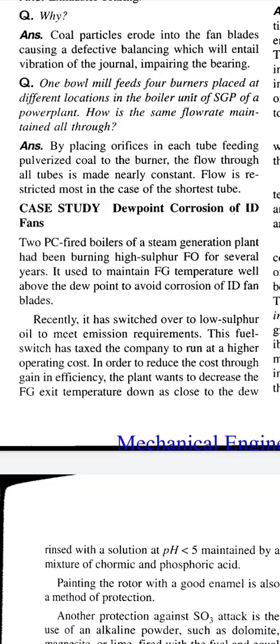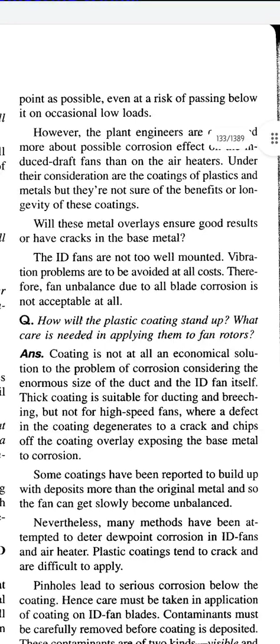This fuel switch has forced the company to run at a higher operating cost. In order to reduce the cost through gain in efficiency, the plant wants to decrease the FG exit temperature down as close to the dew point as possible, even at risk of passing below it on occasional low loads. However, the plant engineers are concerned more about possible corrosion effect on the induced draft fan than on the air heaters.